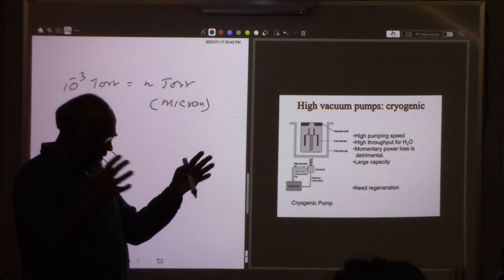So then, because this is your chamber, you need to pump. If you have something very cold, we call it the cold head, connected to this part. Whenever you have a cold surface, any gas molecule will condense onto that surface, that's the whole idea. All the gas molecules will condense onto that cold surface, and that way you can remove them, reduce the gas molecules. That's what pumping means, so it condenses onto this surface and reduces the pressure.